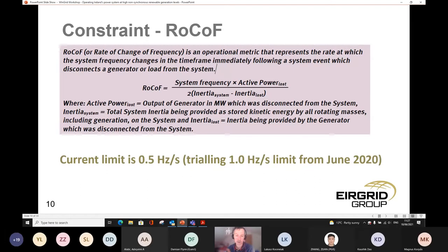This means that for the loss of a large infeed on our system, we can allow a rate of change of frequency of up to 1 hertz per second. This essentially means we can operate a lighter system and accommodate more wind onto the system.